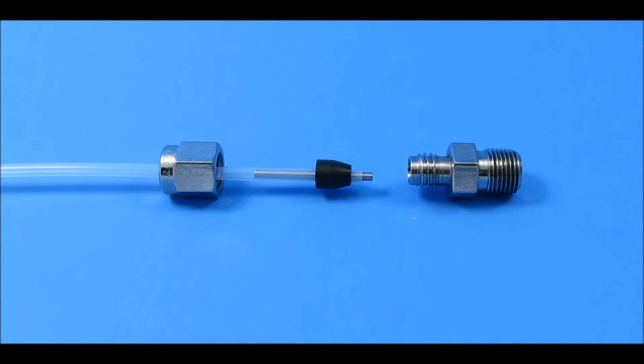The second component is our custom polyimide graphite ferrule which is specifically designed to work with these instrumentation fittings. The third component of the system is the stainless steel insert designed to match the inside diameter of the PTFE tubing and used to compress the ferrule onto the tubing to create a secure connection. Finally, the fourth component is the PTFE tubing.